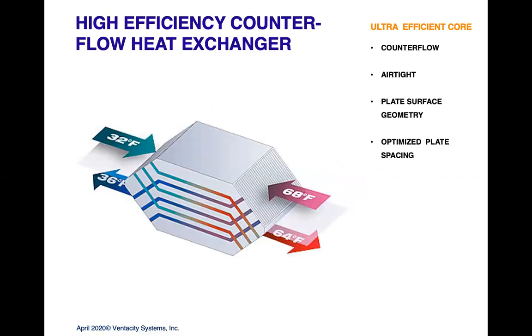The way to get very high efficiency for the most part, with few exceptions, is counterflow heat exchangers rather than crossflow or enthalpy wheels. Swegon has wheels that they've perfected to get very high efficiency and get passive house certified for their HRVs. Their ERVs are not certified, and that probably has to do with something, the dust and moisture. For the most part, they're mostly counterflow heat exchangers like you see here, and that's both HRVs and ERVs.